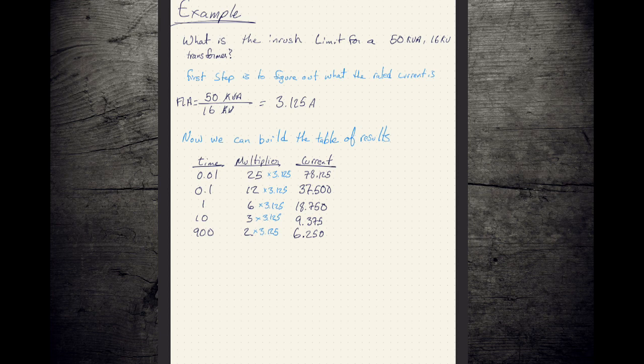So once we have our full load amps for this transformer, we can go to our table. We write out all our times and what our multipliers are for our inrush. Again, we've got our hot and our cold load inrushes. We're going to take those and multiply each line by our full load amps. And we find out that our 3 amp transformer, 1/100th of a second after being energized, is potentially flowing just under 80 amps. And we can see that's going to taper off as time goes.